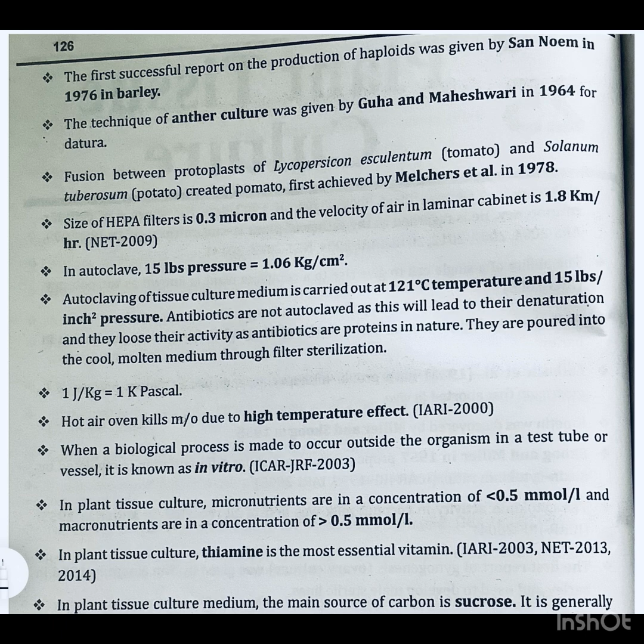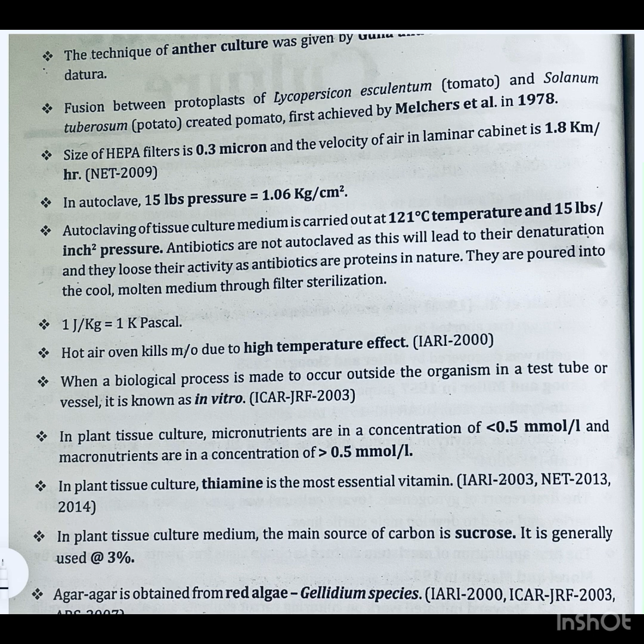In autoclave, 15 lbs pressure is equal to 1.06 kg per centimeter square. Autoclaving of tissue culture medium is carried out at 121 degrees temperature and 15 lbs per inch square pressure. Antibiotics are not autoclaved as this will lead to their denaturation and they lose their activity, as antibiotics are protein in nature. They are poured into the cool molten medium through filter sterilization. 1 joule per kg is equal to 1 kilo pascal. Hot air oven kills due to high temperature effect.